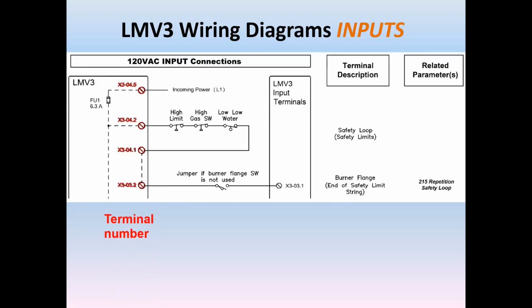120 volt inputs. Each one of them will give the terminal number. In this case, we see the safety loop is a series of terminals, bringing in the safety loop string from 342 to 341, connected to 332, and ultimately input to 331 is the final input of the safety loop string. In addition to the terminal numbers, we give a description. In this case, these terminals are dedicated to the safety loop, and maybe you can detail it and say that it has the burner flange part of the safety loop.